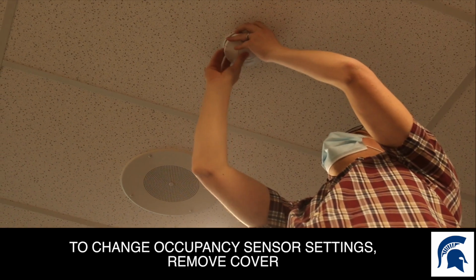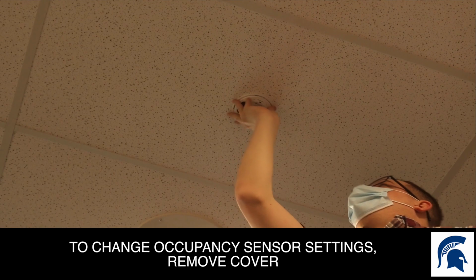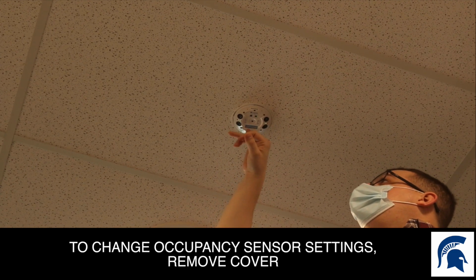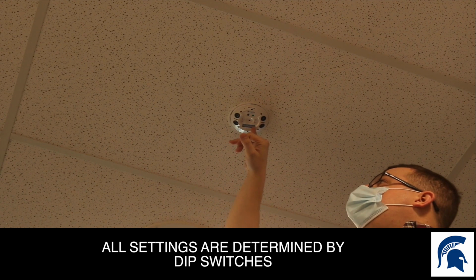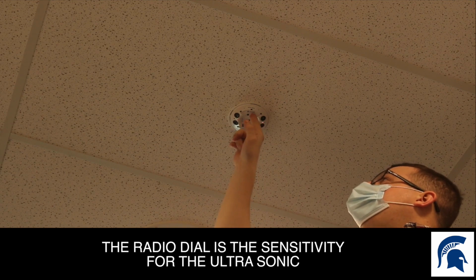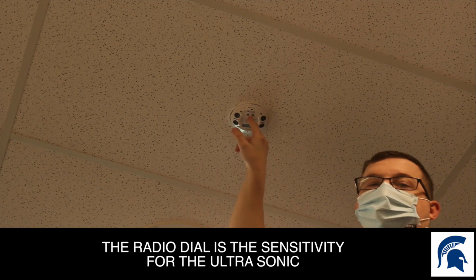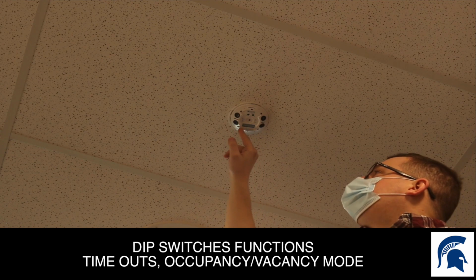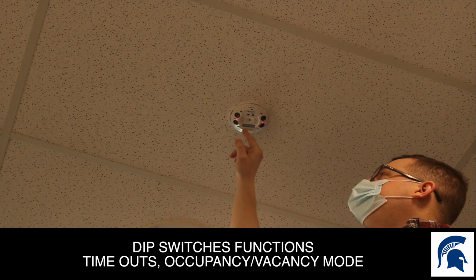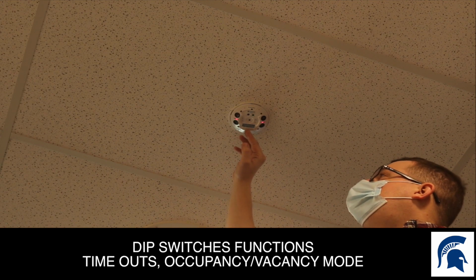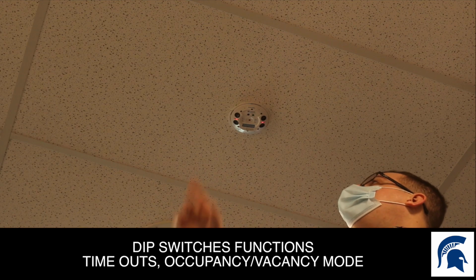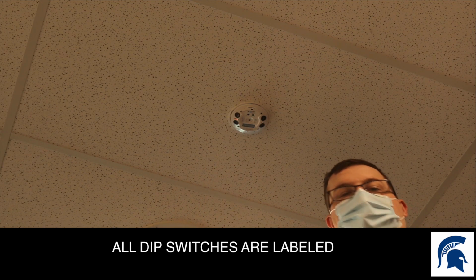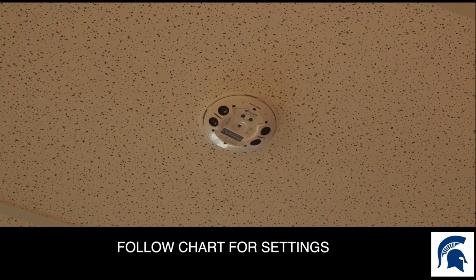To change any of the settings on the occupancy sensor, remove the cover. All settings are determined by dip switches, and then the radio dial is your sensitivity for the ultrasonic. If you look very closely, and we'll get a better picture of this, each dip switch does a certain thing. The first ones do your timeout, occupancy vacancy mode, and so on. Everything is labeled on here, and you just follow the chart to set your settings to what you would currently want them to. Right now it's set for occupancy with a 10-minute timeout.